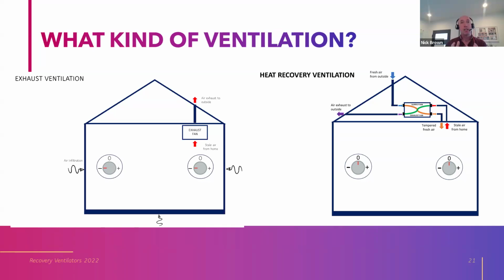So that means that you're going to need to either install a MERV 13 filter in an aftermarket way if your recovery ventilator isn't equipped with that, or hopefully you find a manufacturer that has that as an optional module. Because recognize that outside of the state of California, no one's requiring MERV 13 on these systems. I found a manufacturer that'll make them to fit the HRV in my house, and I just order these MERV 13 filters as needed to fit my recovery ventilator, because it did not come with that standard.